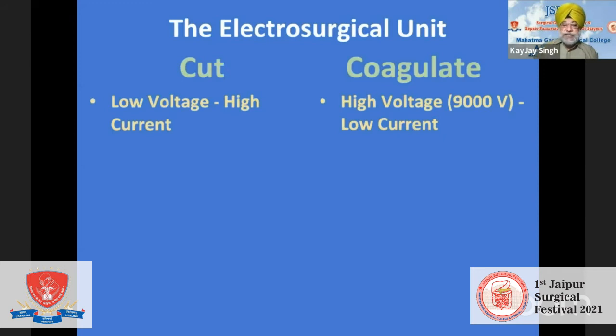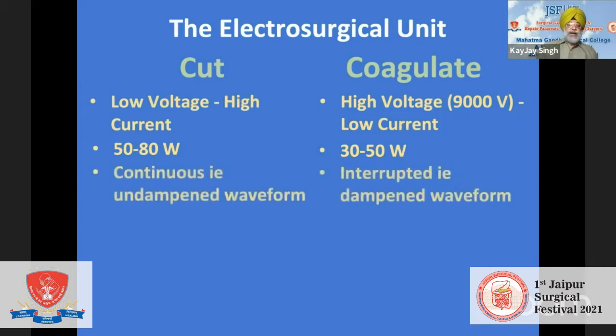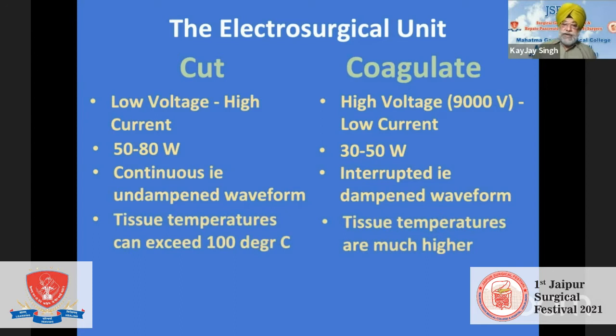So now getting on to the electrosurgical unit, we all know that it's got two modes, cut and coagulate. They have different settings and they are very specific for usage. The cut has low voltage, high current, and the coagulate has high voltage, low current, and the voltage in coagulate mode can go up to 9,000 volts. The cut works at a power of 50 to 80 watts, and the coagulate works at a power of 30 to 50 watts. The cut mode is a continuous undampened waveform, and the coagulation mode is an interrupted dampened waveform. This is very relevant. I'll come to it a little later.